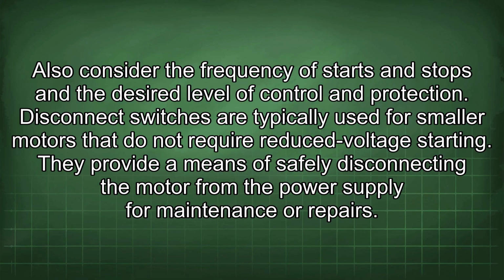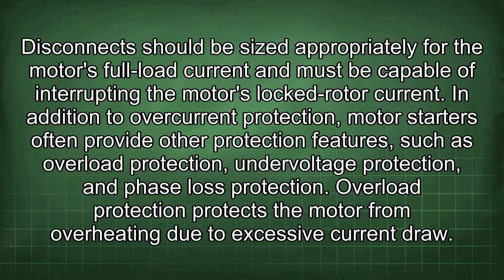Disconnect switches are typically used for smaller motors that do not require reduced voltage starting. They provide a means of safely disconnecting the motor from the power supply for maintenance or repairs. Disconnects should be sized appropriately for the motor's full load current and must be capable of interrupting the motor's locked rotor current.